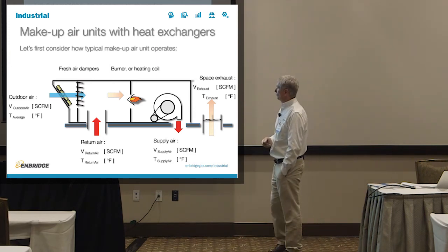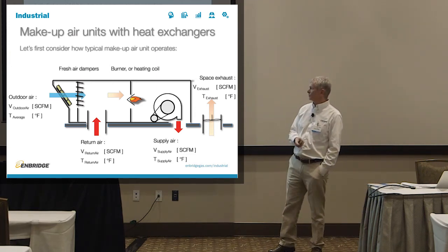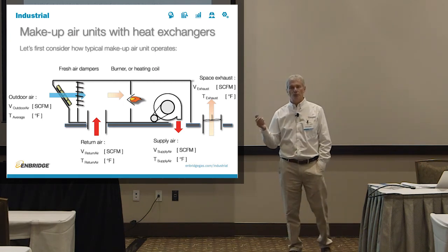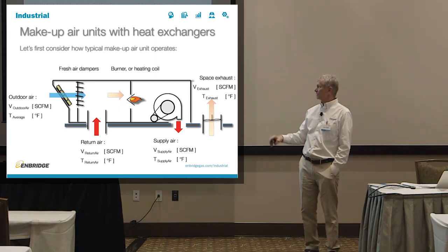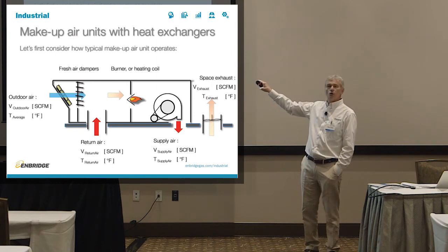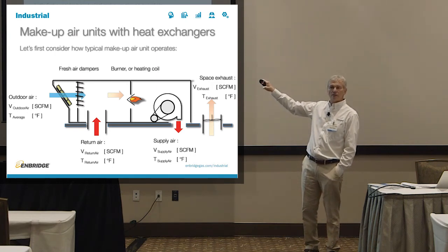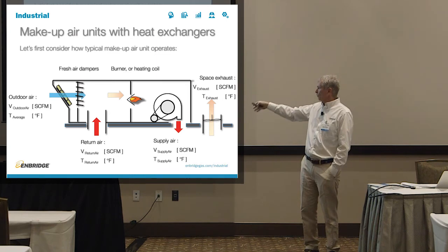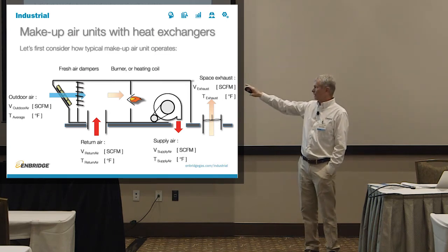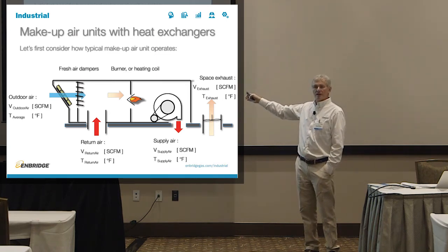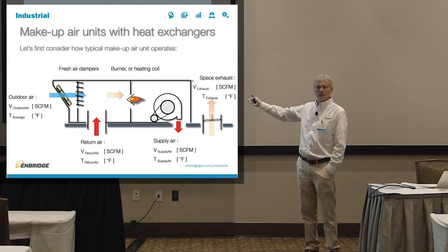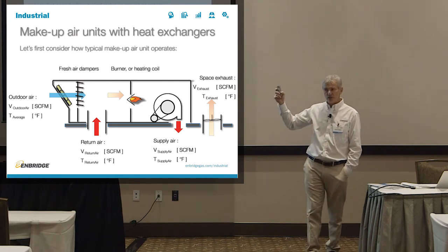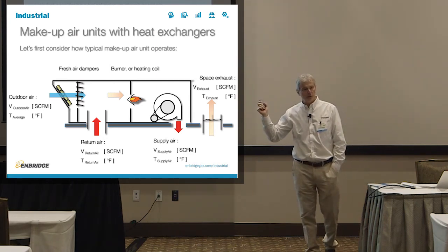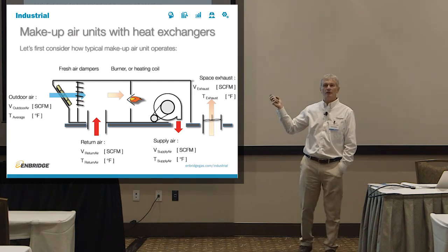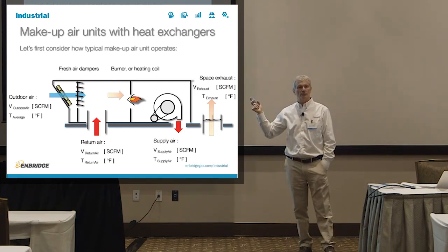So if you have a roof, let's first see how the makeup air unit works. You take the outdoor air, you put it through the filters, through some fresh air dampers, you put it over the direct fire burner, and you blow it into the system. So you take outdoor air and you create supply air that's heated and goes into the facility. Sometimes you have some return air, sometimes you don't. Before you recover heat from your makeup air units, be aware of how much return air you have and how much fresh air you have.